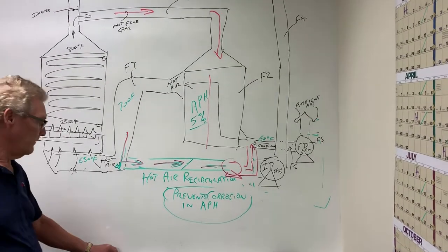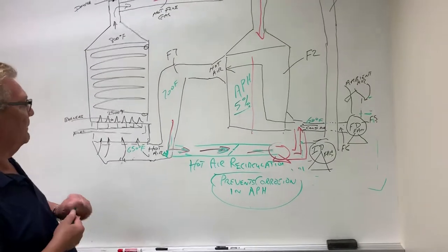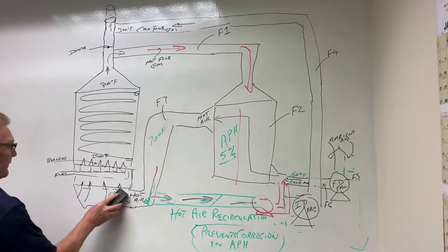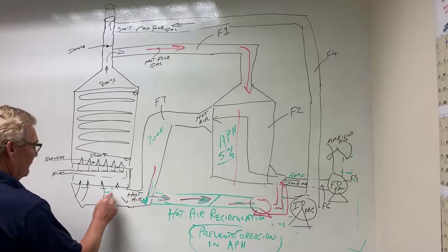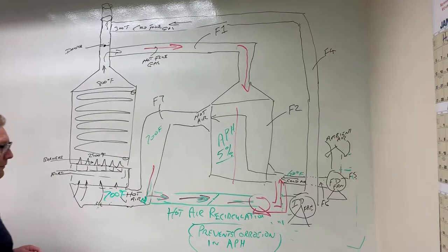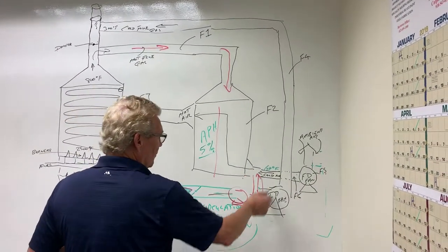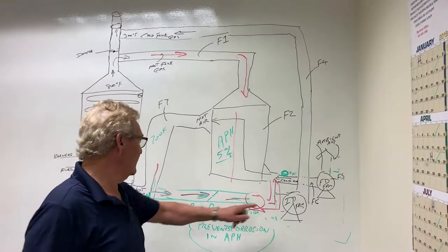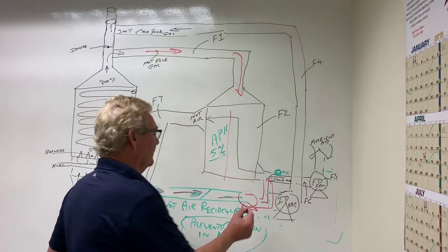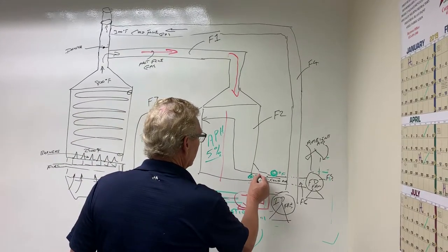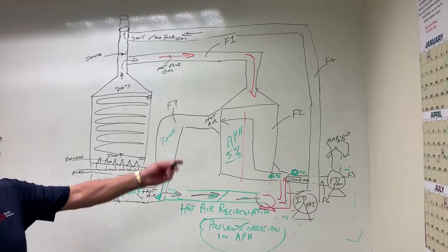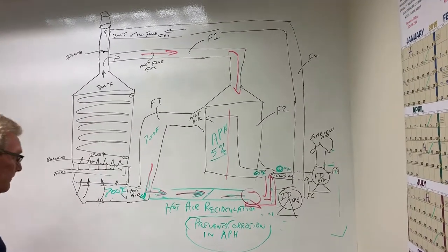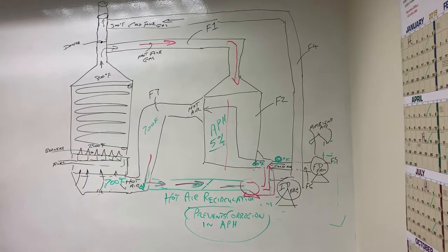Would the temperature change to the burners? We size it so that typically the hot air going to the burners stays the same at 700 degrees. So this becomes 700 degrees still. Okay. Basically, while we've got 60 degrees here, when this is really sized, this could be 0 degrees F here. But then we recirculate enough hot air around to bring this back up to 60 degrees or higher before it hits the heat exchanger. Okay, so this is usually convenient for places up north or that have colder temperatures, snow, etc. Exactly. Okay.